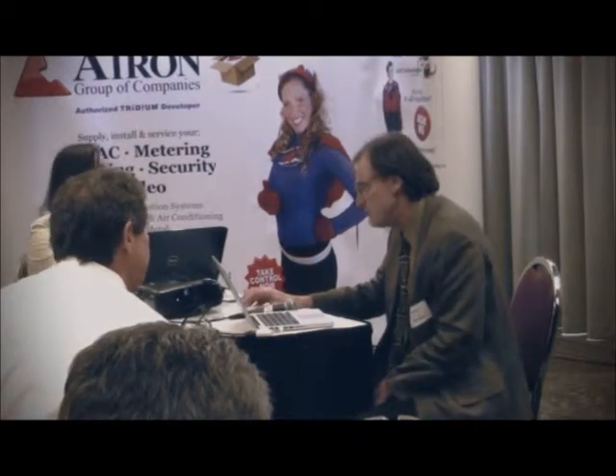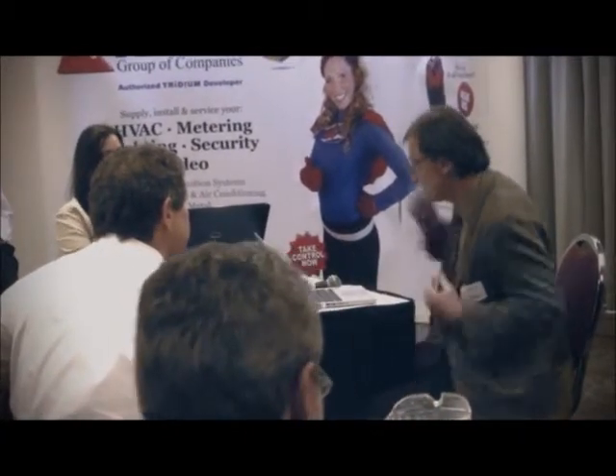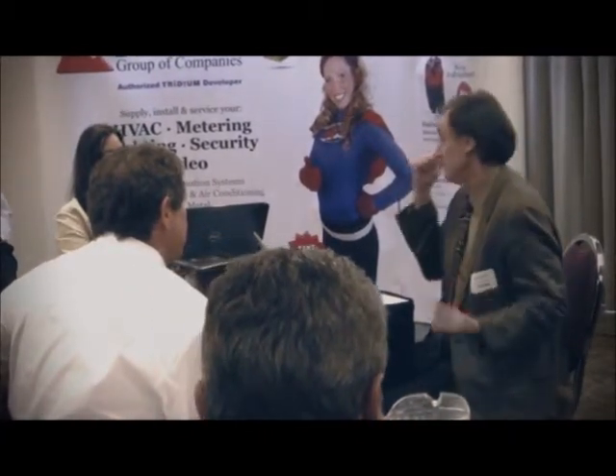What's that rule mean? It means that the AHU has a component on, but there's no proof of run from the fan. Well, I can see an interesting pattern here right away. During the 4th short cycle event on the AHU, we also got a proof of flow fault. So this thing's cycling and cycling, and the flow switch is dying because of it, and it didn't trigger.